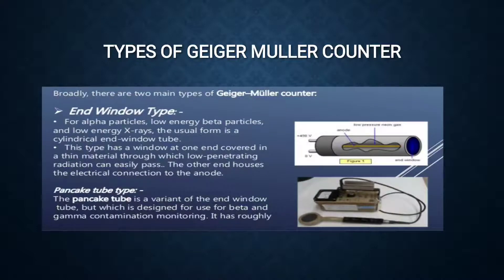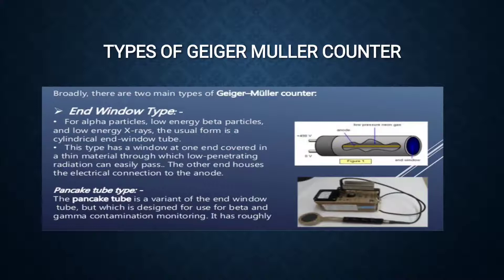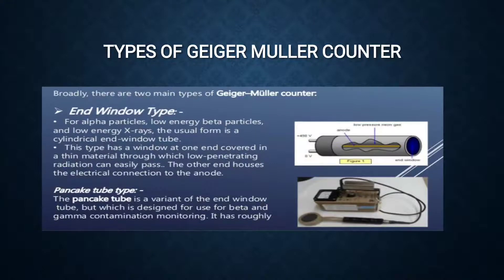There are two types of Geiger-Müller counters: the end window type and the pancake tube type. The end window type is usually used for alpha particles, low energy beta particles, and low energy x-rays. It has a cylindrical form with a window at one end covered by a thin material through which low penetrating radiation can easily pass, and the other end houses the electrical connection to the anode. The pancake tube type is a variant designed mostly for beta and gamma radiations.